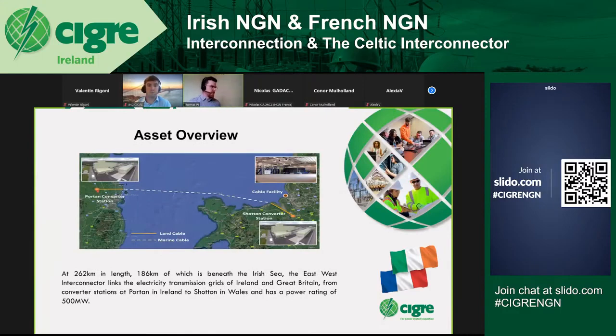The cable portion of the asset is 262 kilometres in length, running from Portan in County Meath to Shotton in Wales. It makes landfall at Rush Beach in North Dublin and at Prestatyn in Wales. We have converter stations in both Portan and Shotton, plus a cable spares facility in Liverpool which we mobilise from in the event of a repair operation. EWIC connects the power grids of Ireland and Great Britain, with a power rating of 500 megawatts.